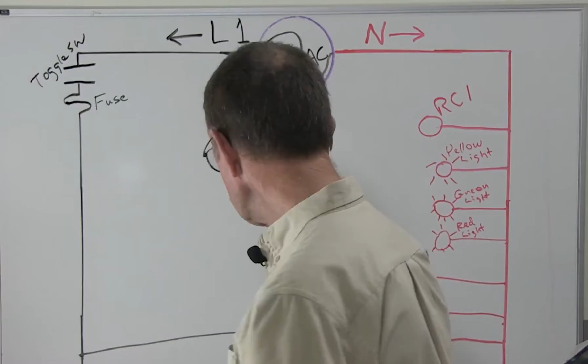So I know that when this relay is not energized, I have a circuit from point 4, L1, go through the switch, come out of the switch, and go to one side of the orange light. I've got another circuit I can fill in. I know what I got here now. I've got one side of the switch. Boom, done deal. Oh, and that was a normally closed switch, by the way. So that's relay coil 1, normally closed, all right?